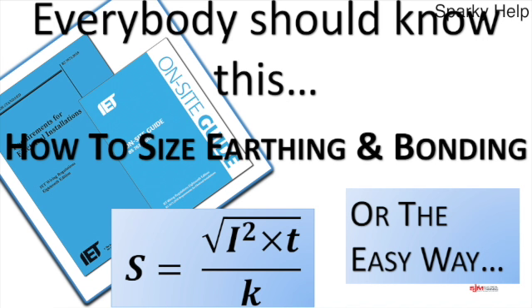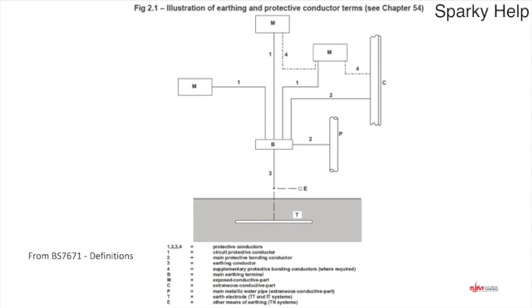In this video we will look at sizing earthing and bonding conductors. We can do it the easy way or we can do it the adiabatic way, but we'll also look at how to size earthing conductors and supplementary bonding conductors and also main equipotential bonding conductors. So before we do that, we need to look at each of those conductors and remind ourselves what they all are. So let's start with number 3, right in the front there at the very bottom, and that connects to B, and B is the main earthing terminal, and number 3 is your earthing conductor.